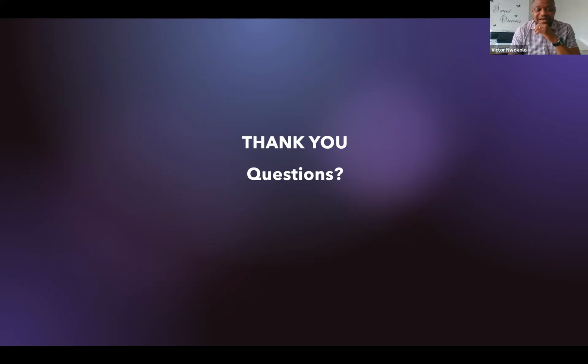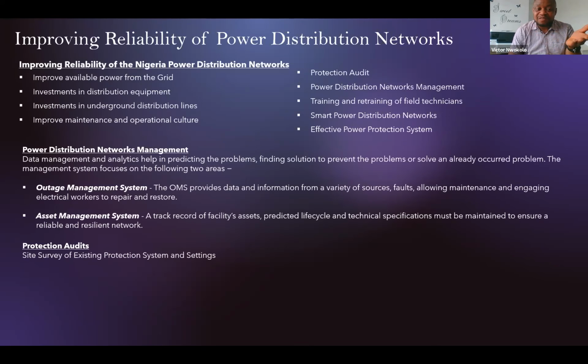Availability versus reliability. For how to improve power, it's one of the things that I mentioned. Availability, we have to improve available power at the generation end first, then improve the transmission to be able to carry that available power, then improve on the distribution network to be able to deliver that available power. But as it is just now, based on what is available in the grid or to the local discos, sometimes within that supply, they still lose supply to certain areas due to faults. So the power may be available temporarily, but you hear cases of blown transformer.